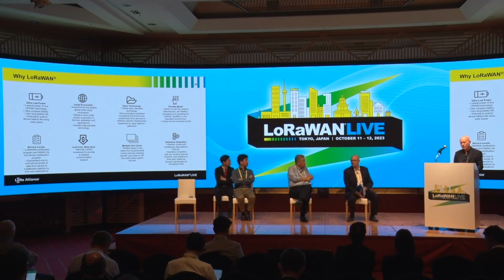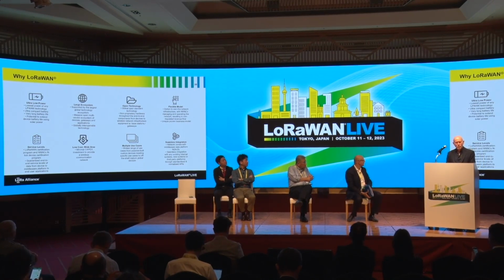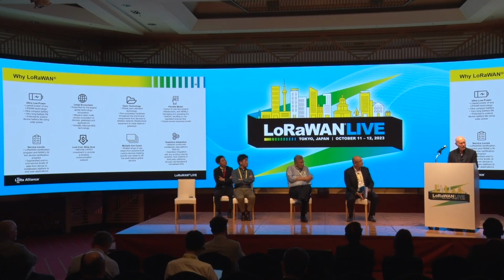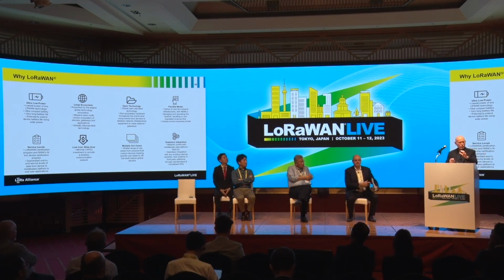So I'm not going to go through all of these, but the big thing that is why LoRaWAN for utilities is in all of those electricity use cases I mentioned before. In each case, we are harvesting the existing power from the network. You can't do that with an NB-IoT device. There's just too much power required to harvest in a non-invasive way. In other words, we're just using current transformers. So you can't do that because you need too much power to do that with an NB-IoT type device. So LoRaWAN is uniquely positioned to service something where you need to harvest energy from an external source.